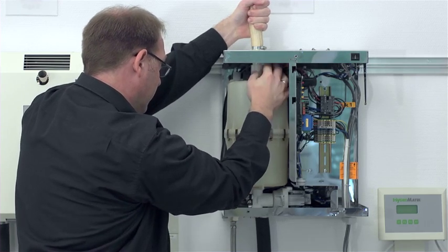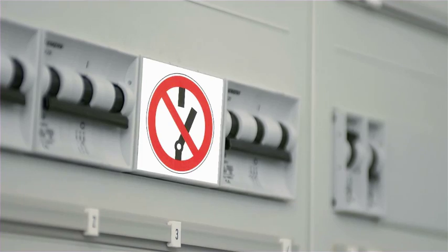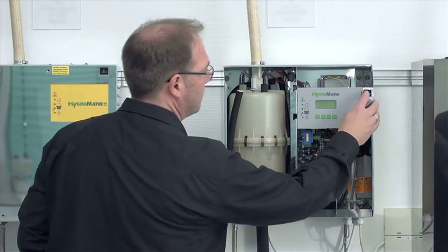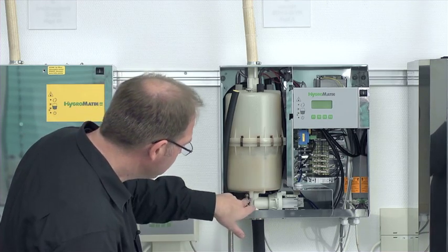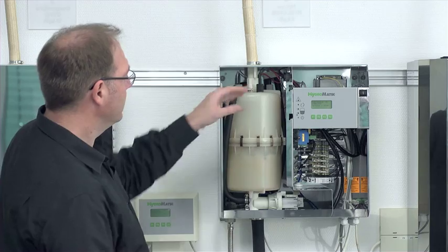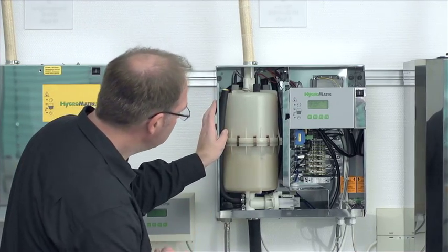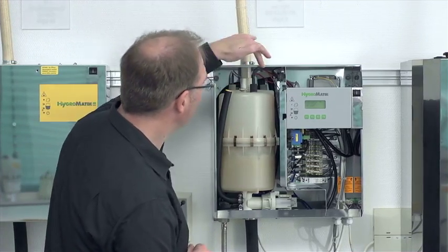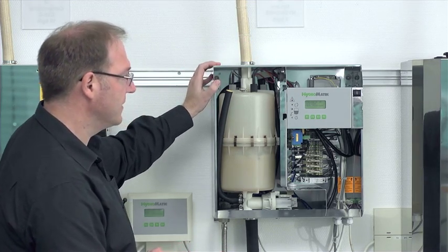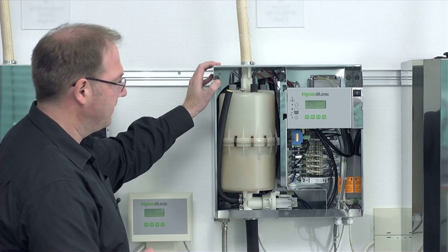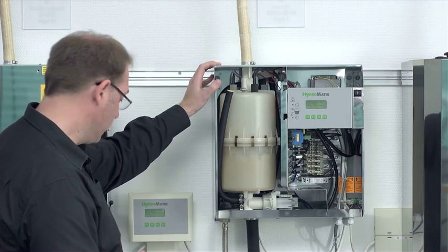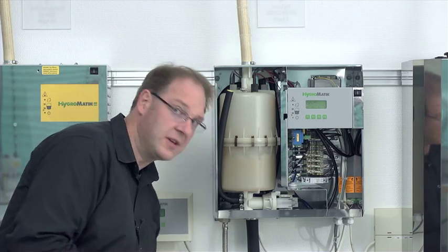After I've now remounted the steam cylinder, I restore power to the unit to let it run a test phase. I take a look at all the hoses where we have replaced the seals and check if there is water leakage anywhere. If not, then so far all is in order. I check again if all cables are lying properly and that nothing is squashed anywhere.